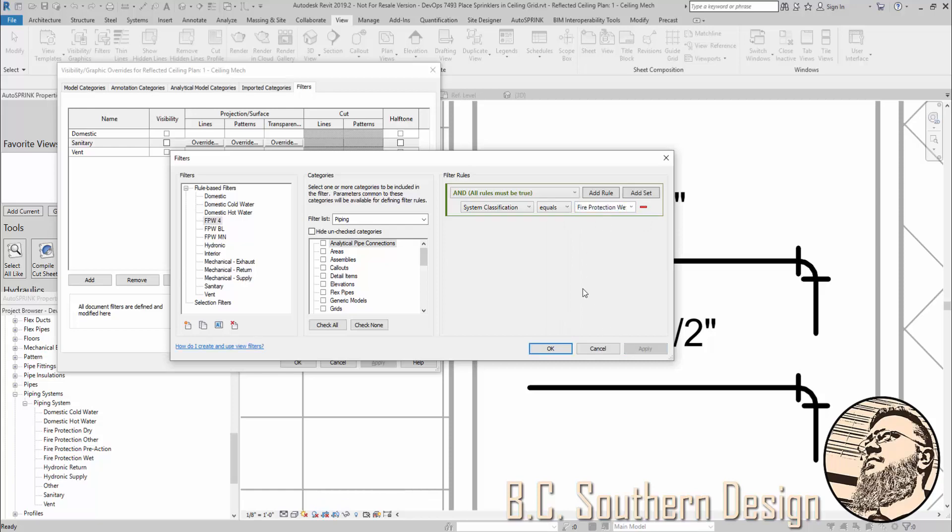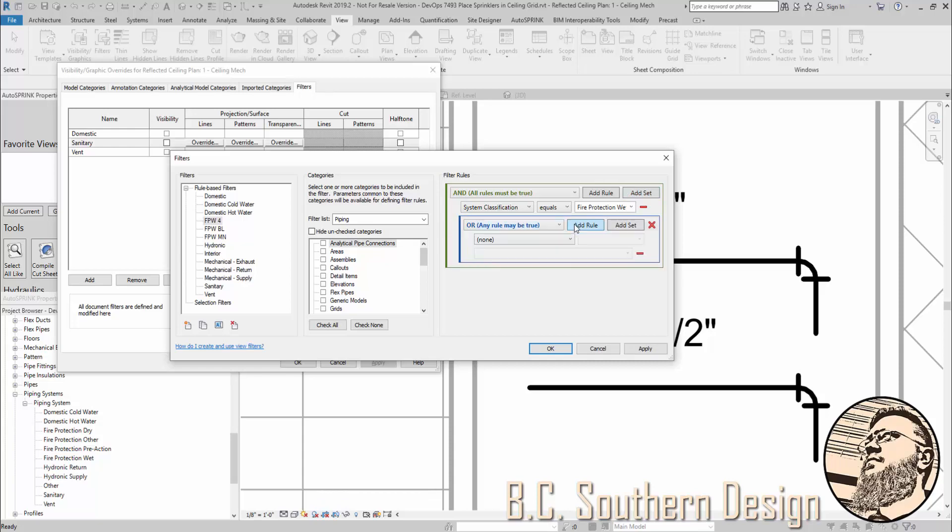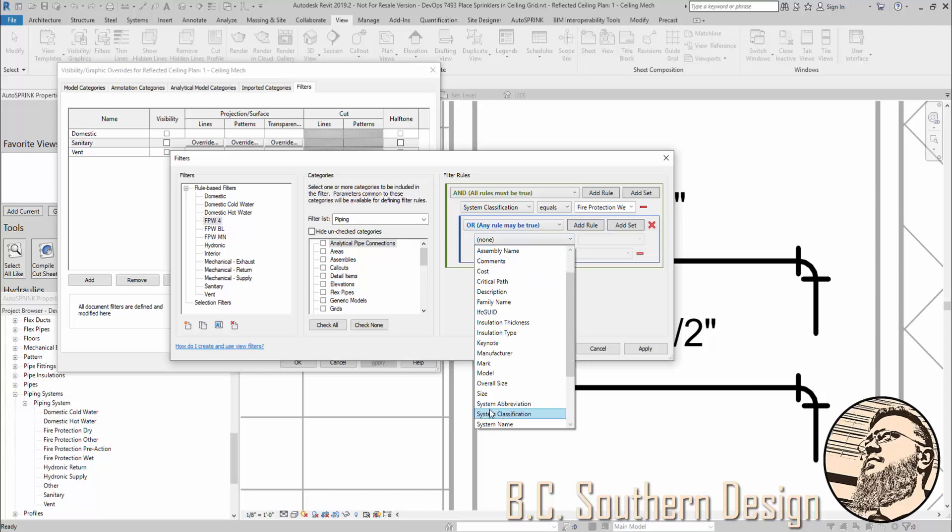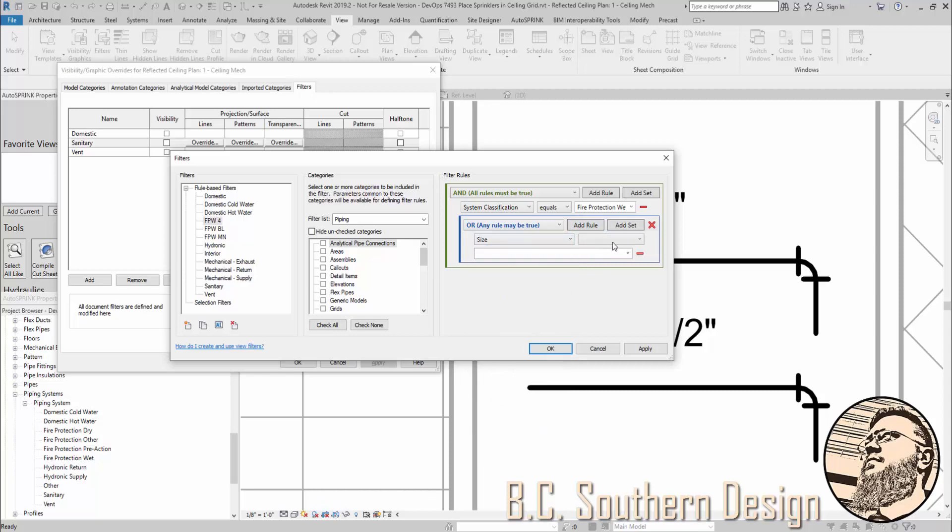And I want this to apply to pipe fittings as well as pipes. Now, first rule. Only if it's part of fire protection wet do I want this to even bother. But then, I want it to only be for 4 inch pipe and fittings. Now, I'm going to do the sizes of pipe as a set. And I'll show you why. Because if I were to say, I want the size such that it equals 4, that's great. However, even if you have a straight fitting, like an elbow that's going from 4 inch to 4 inch, Revit doesn't see it that way. It doesn't see it as just a 4 inch. It sees it as a 4 inch by 4 inch.